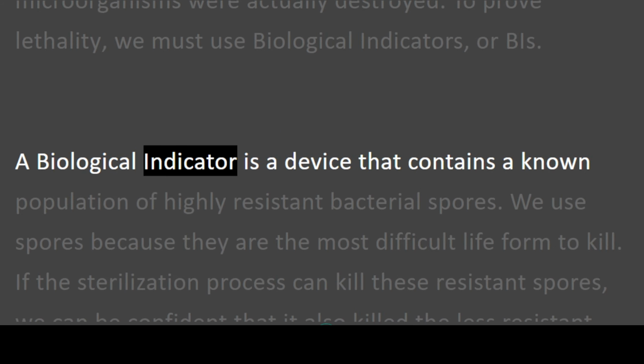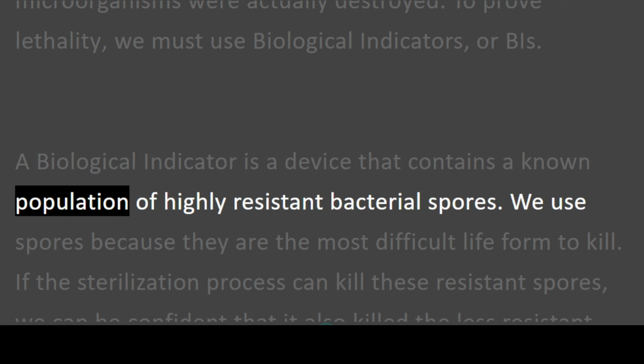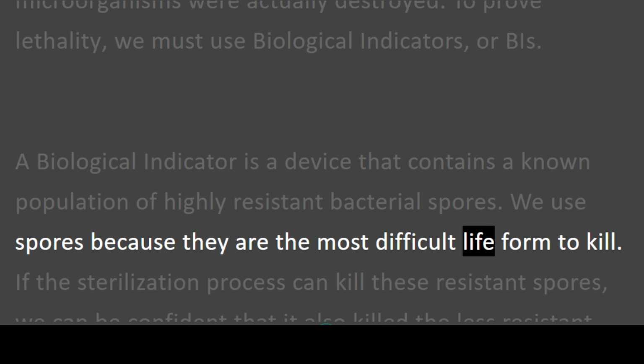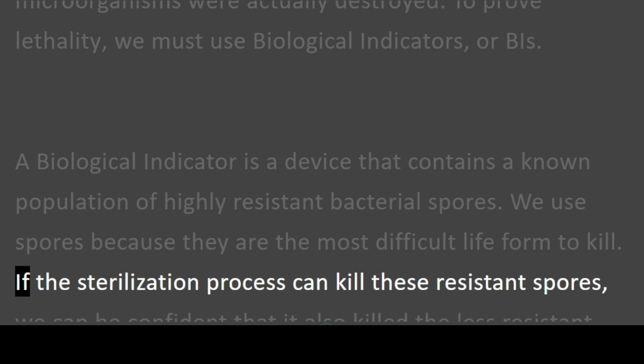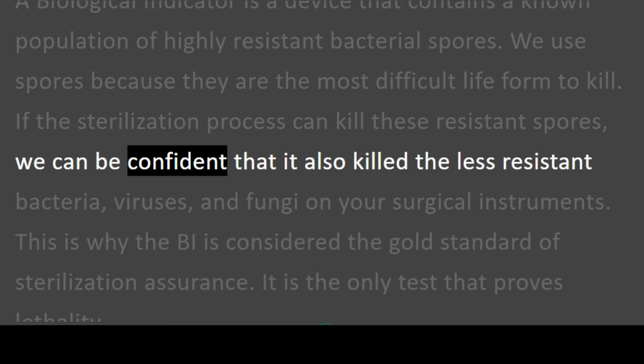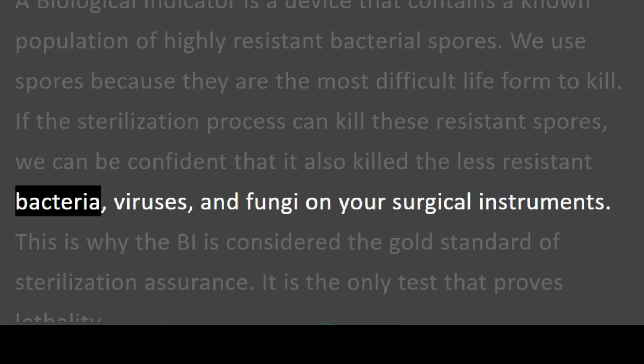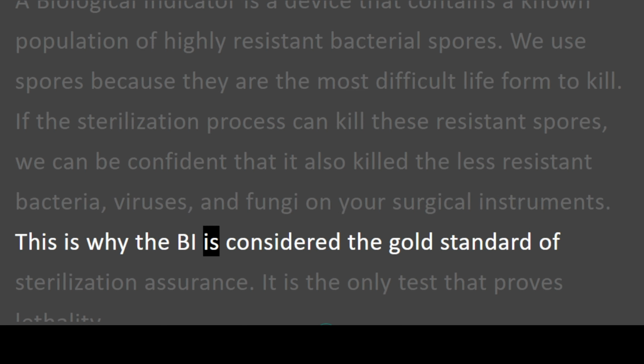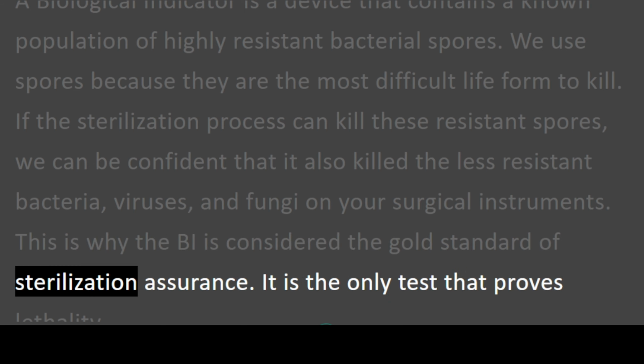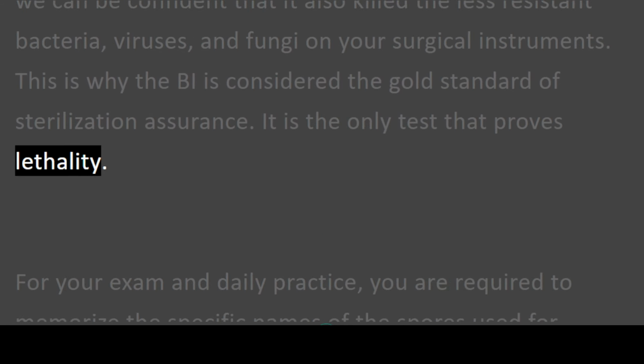A biological indicator is a device that contains a known population of highly resistant bacterial spores. We use spores because they are the most difficult life form to kill. If the sterilization process can kill these resistant spores, we can be confident that it also killed the less resistant bacteria, viruses, and fungi on your surgical instruments. This is why the BI is considered the gold standard of sterilization assurance. It is the only test that proves lethality.